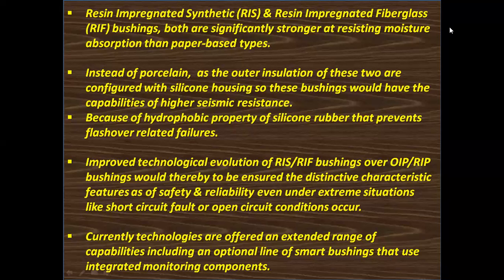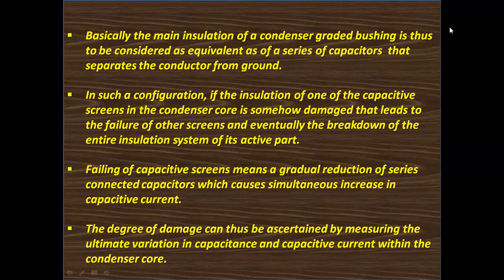Currently, technologies often offer an extended range of capabilities, including an optional line of smart bushings that use integrated monitoring components. Basically, the main insulation of a condenser graded bushing is considered equivalent to a series of capacitors that separates the conductor from ground. In such a configuration, if the insulation of one of the capacitive screens in the condenser core is somehow damaged, that leads to the failure of other screens and eventually the breakdown of the entire insulation system of its active part, that is the condenser core.